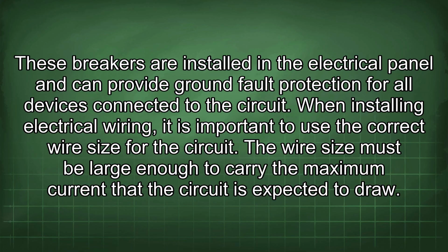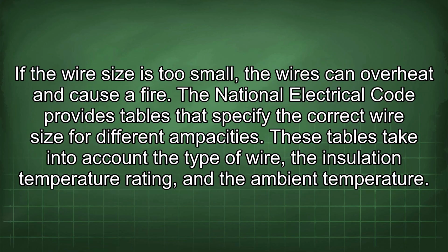The wire size must be large enough to carry the maximum current that the circuit is expected to draw. If the wire size is too small, the wires can overheat and cause a fire. The National Electrical Code provides tables that specify the correct wire size for different ampacities. These tables take into account the type of wire, the insulation temperature rating, and the ambient temperature.